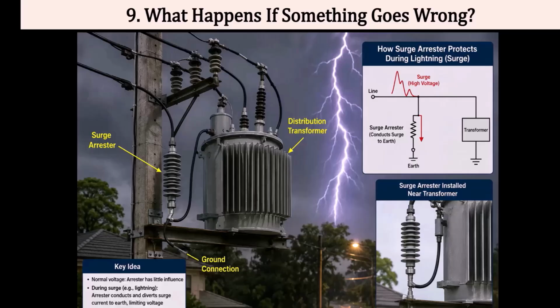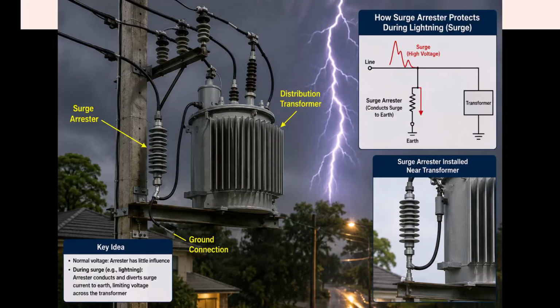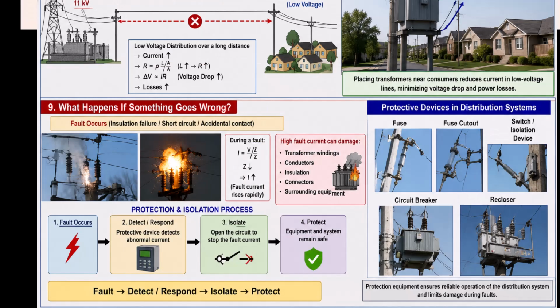What happens if something goes wrong? Everything sounds good so far, but an electrical engineer should never ask only how does it work. We must also think about what happens when it fails. Suppose insulation inside the system fails, or two conductors accidentally make contact, or some other short circuit condition develops. What happens to current? Remember, I is equal to V divided by Z. During a short circuit, the effective impedance may become very small. Therefore, if the impedance value decreases, the current will increase, potentially very rapidly. The large fault current can damage transformer windings, conductors, insulation, connectors, and surrounding equipment. So the system requires protection and isolation.